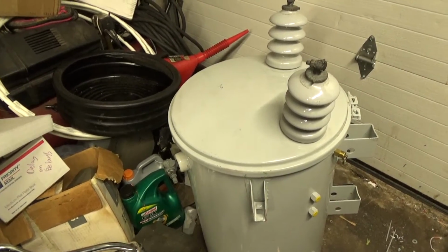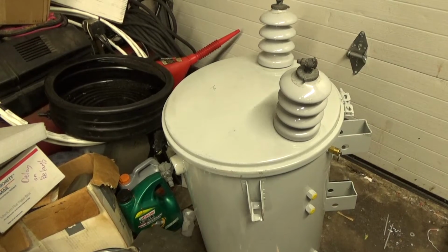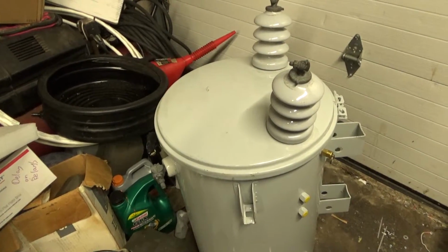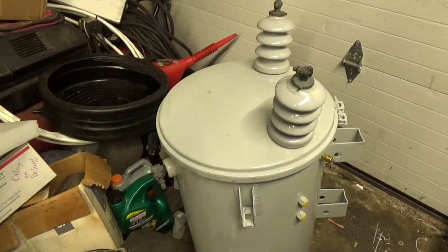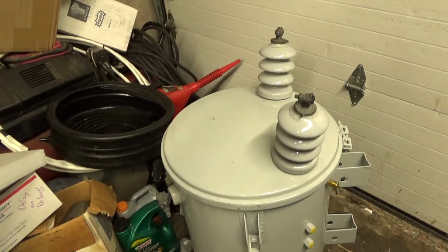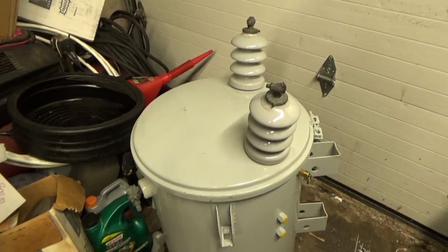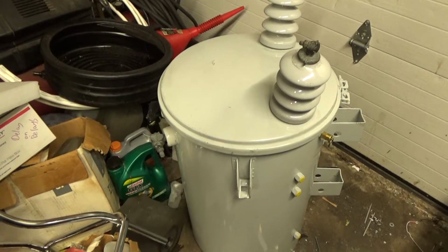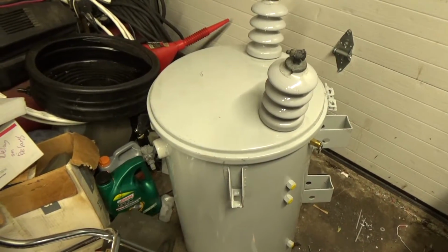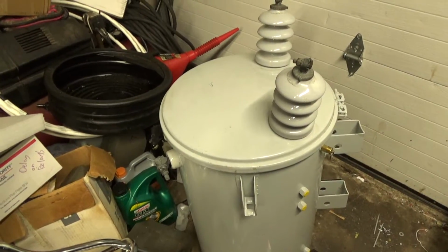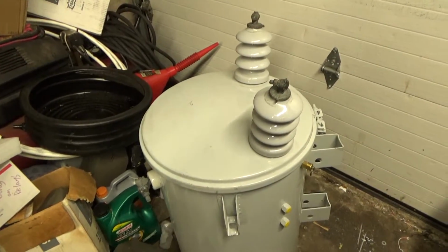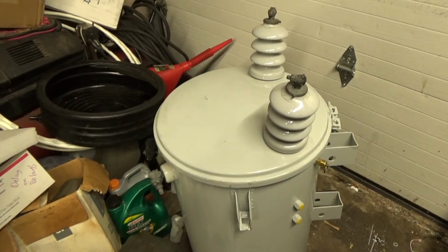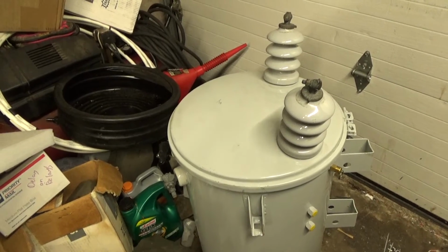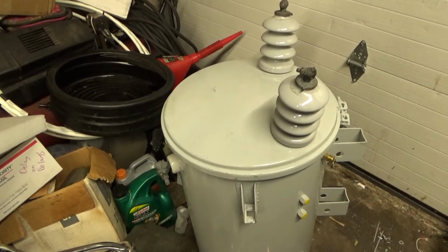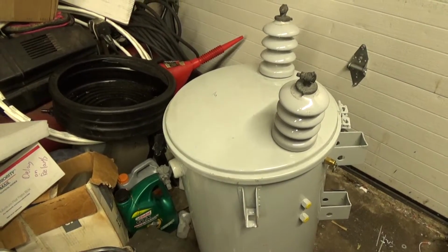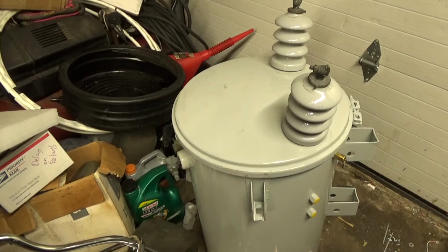The oil increases the dielectric properties between the windings, the turns, the transformer turns. It's basically a coil wrapped around a core. So once the transformer flashes, it's done. It's shot. It's no good. So if you're going to run one of these, you have to run it in the can. See, the insulating material is actually designed to absorb. So once all the oil's gone, it will absorb moisture from the air, and then it will end up flashing.